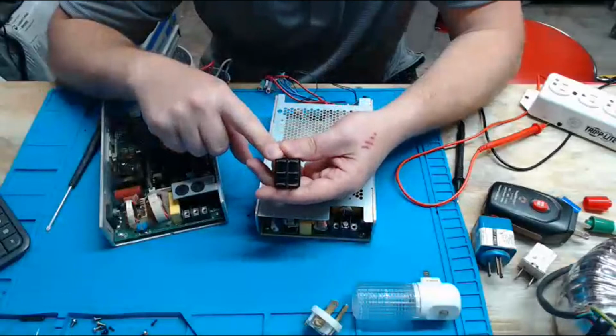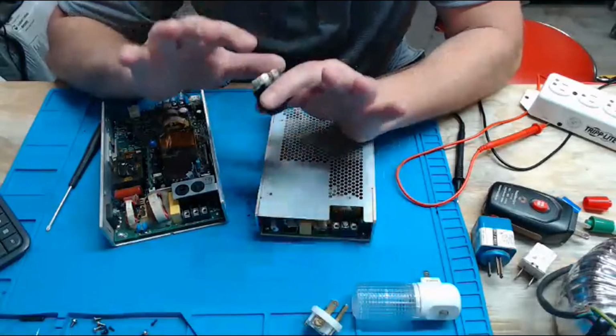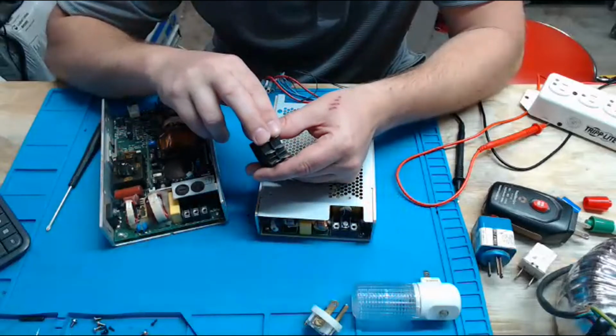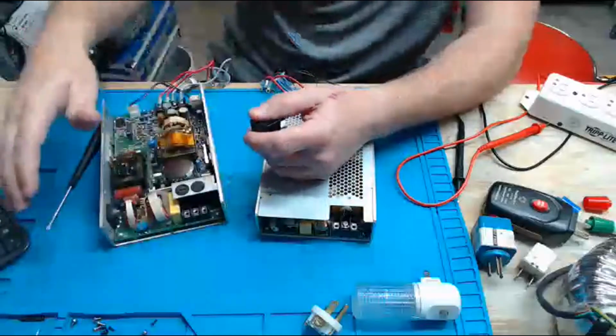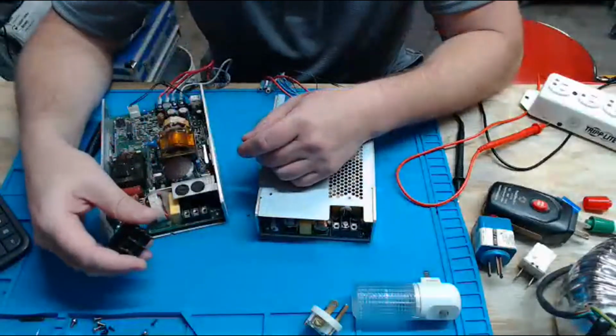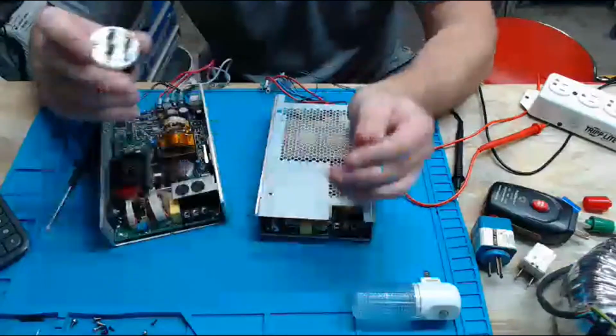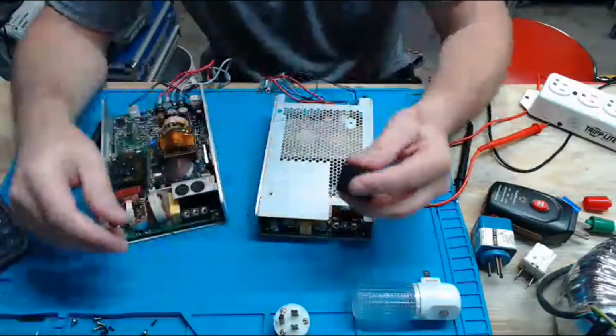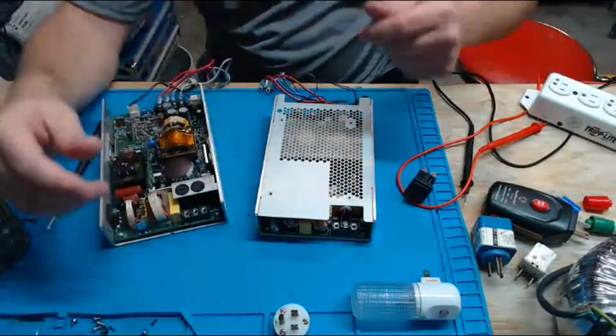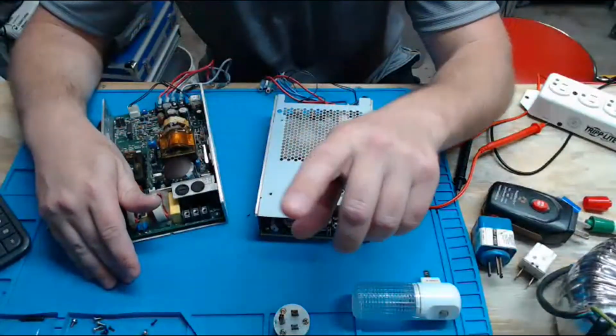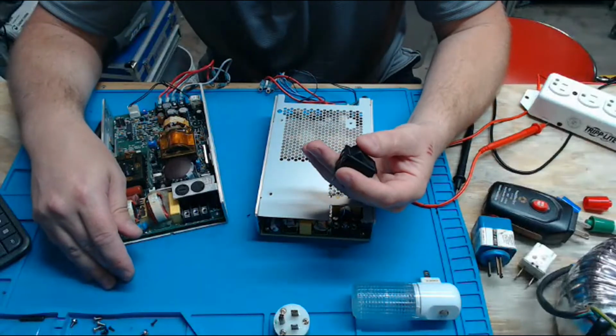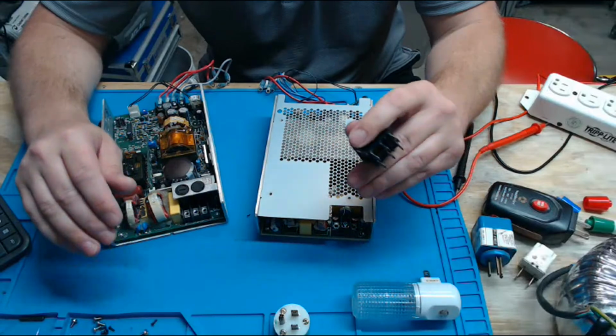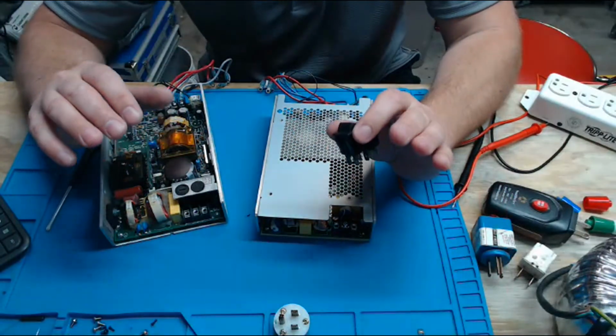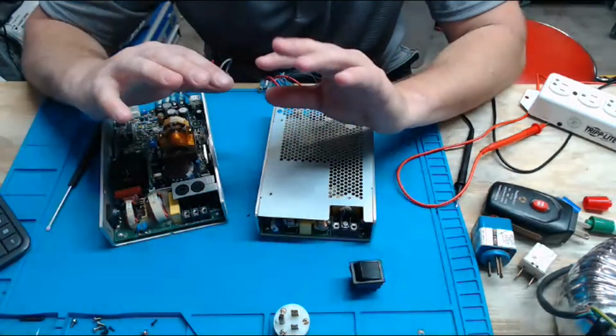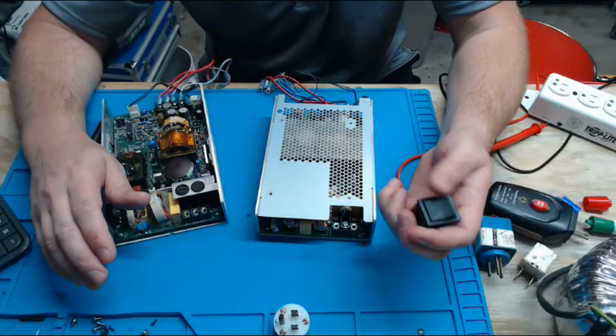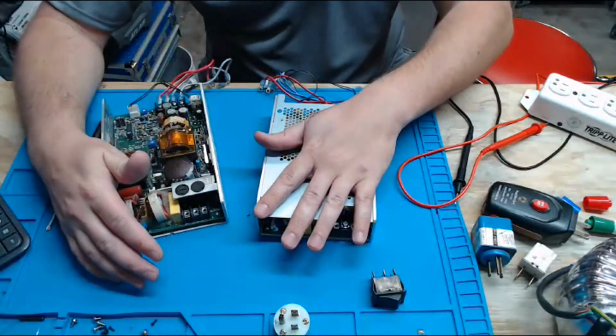And power switches, guys: on many, if not most, medical devices, line and neutral are both going to be switched. So we disconnect all the power from the entire unit, because of human error. People can always accidentally snap off the ground, plug it in upside down, whatever. So we want to kill both line and neutral so we don't end up with that situation like I showed on the whiteboard, where we have line power running through the device even though the power switch is shut off. It can happen. Medical devices have such special electrical code, and once you really start paying attention to how much detail they put into the design of medical devices, you really get to appreciate all the thought that's gone into these devices and why we're special.